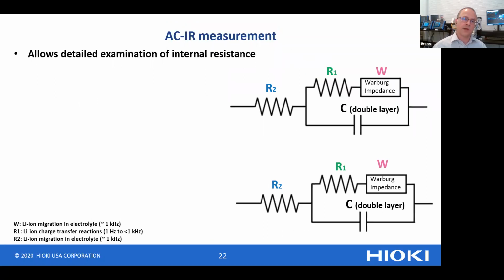On the other hand, there's also another method called the AC-IR measurement method. And in this case, we use an alternating current to measure the impedance. And this allows for a more detailed examination of the internal resistance of the battery. For instance, if we look at the battery model here on the right, at very high test frequencies, the impedance of the capacitor drops so low that it's essentially a short. So the majority of the current takes this path along R2 and through the capacitor. So at very high frequencies, we can evaluate R2, which is the lithium ion migration in the electrolyte.